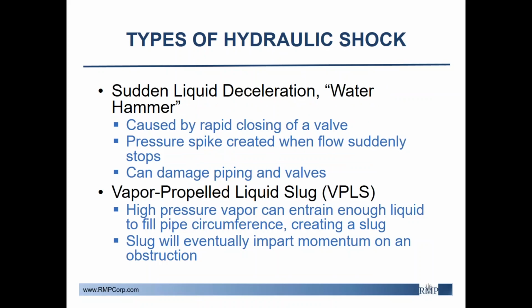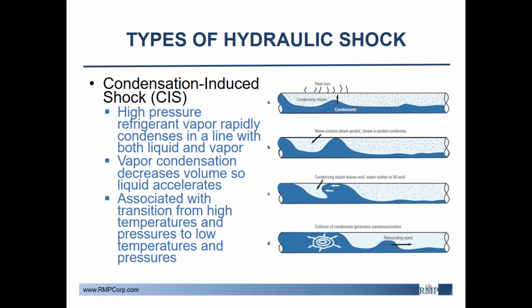Vapor-propelled liquid slug is caused by the entrainment of liquid on high-pressure vapor. Enough liquid will fill the pipe circumference to create a slug, which will eventually impart a large momentum on whatever obstruction it meets, which can be anything from a valve to an expensive piece of process equipment, like evaporator coils, for example.